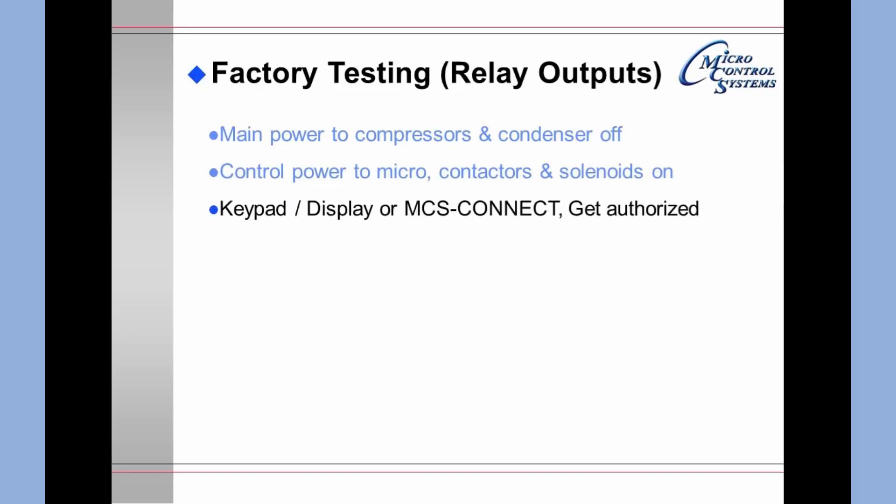On the keypad or display or using MCS Connect, you need to get authorized. Put each relay output in manual on and verify that the correct contactor or relay or solenoid has pulled in. Do not skip any step. You must verify that if you're on a screw compressor and you turn on a load solenoid, it is the load solenoid that came on. If you are on reciprocating compressors, you have to verify that the right unloader has come on, etc. Then put each output back in auto.